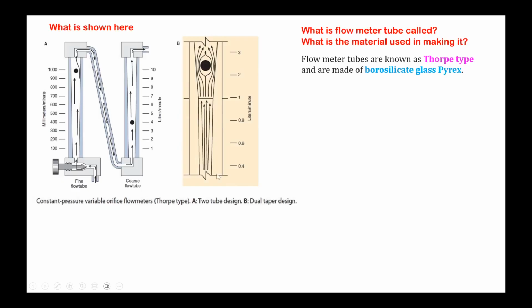So when there is a single flow tube, there is a dual tapering. And see here at the bottom, it is narrow. As it goes up, it widens, so that the higher flows can be accommodated. So what is the physical principle involved in the dual taper design? What factors govern the flow of gases through this dual taper design of flow meters? If it is low flow, it is viscosity. If it is high flow, it is density.